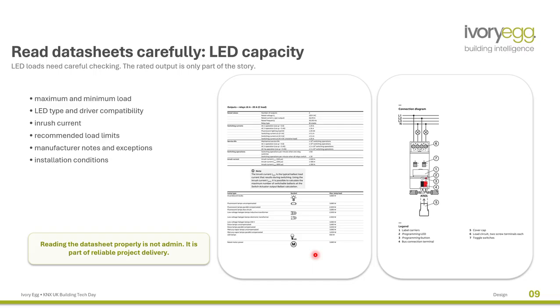For example, this is one of the strongest switch actuators in KNX. On each line you can switch up to 3000 watts on and off. But if it's an LED load rather than a resistive load, this drops to 600 watts. So you should take care about this.